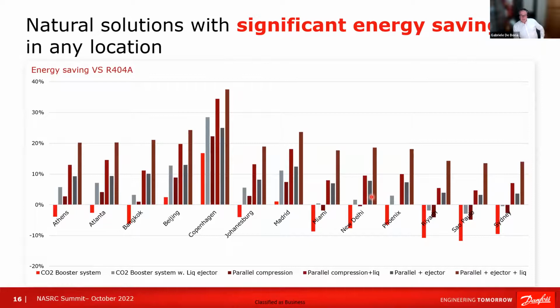I want to show you now some data relating to the performance of a CO2 system. As I was saying before, unfortunately it's not possible for one single solution to fit all the possible environmental and application conditions. So in this graph, each bar represents a different CO2 system: the standard booster system, which is a standard transcritical unit; the transcritical unit with liquid ejector; the transcritical system with parallel compression; then parallel compression with liquid ejector and high pressure ejector; and the full set of parallel compression, liquid ejector, and gas ejector.